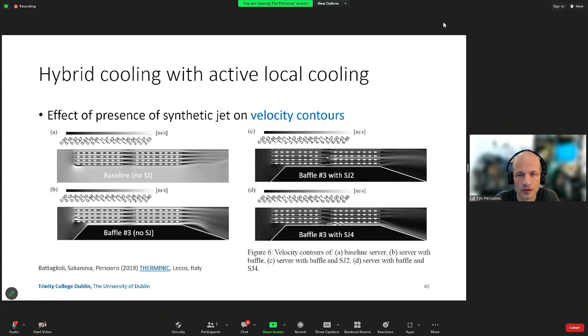Sample results here, and these are velocity contours at first. On the left, we have no synthetic jet, so again the baseline geometry with the empty space in the middle. Then the modified geometry, still without a synthetic jet, but with a baffle here to channel the flow through the DIMM banks, apologies. And then on the right-hand side, we have the same baffle, but with a synthetic jet either in the middle here or over here in this location. We were looking to, again, maximize the uniformity of the flow at the outlets, and also improve the cooling performance in the second DIMM bank.